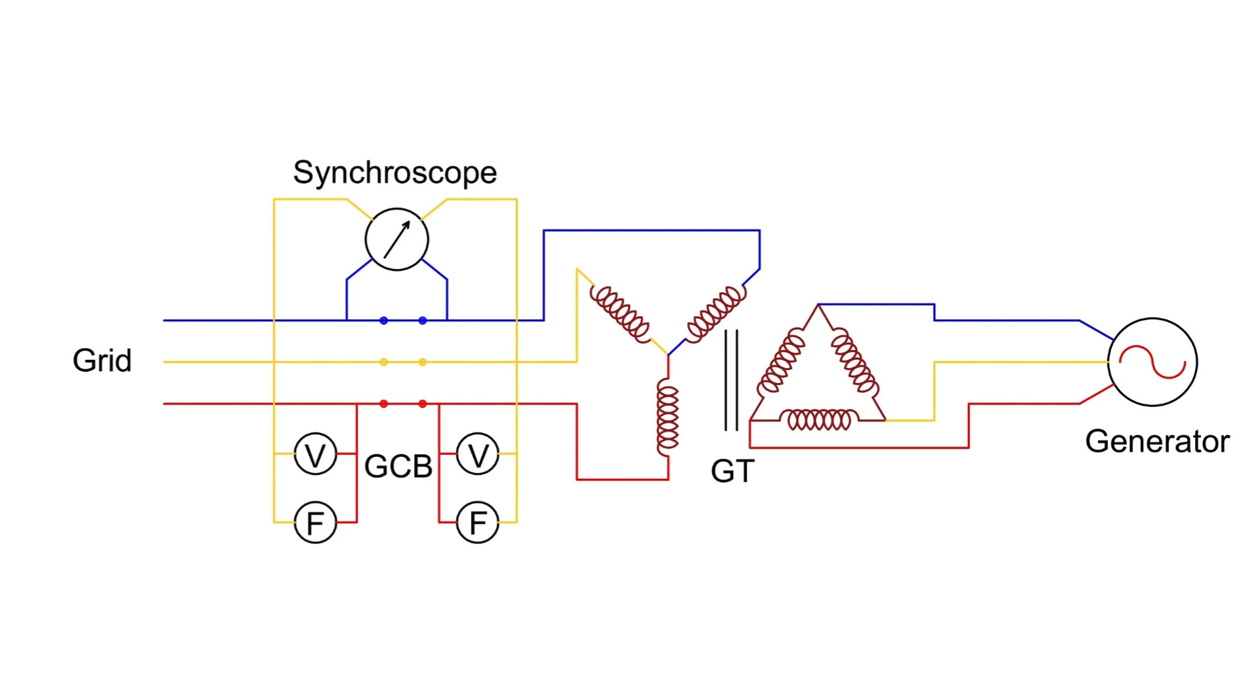Once synchronized, the voltmeter and frequency meter readings on both sides will match, but the generator won't supply or absorb power. This is known as the floating condition.